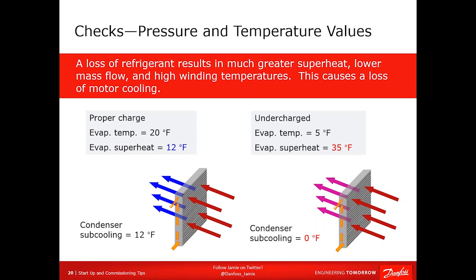Everything is fine. Let's move on to what you'd see with an undercharge system. So your first point of evidence is your 5-degree evaporator temperature. Now, there's lots of things that can cause 5-degree evaporator temperature, like a loss of airflow, right? That will cause your load to drop, your TXV to close down, and the compressor to reduce your evaporator pressure to balance its pumping capacity. However, with low load, there's one thing you won't see, and that is a low evaporator superheat, or sorry, a high evaporator superheat. With low load, you're going to see 9 degrees of superheat or 8 degrees of superheat.